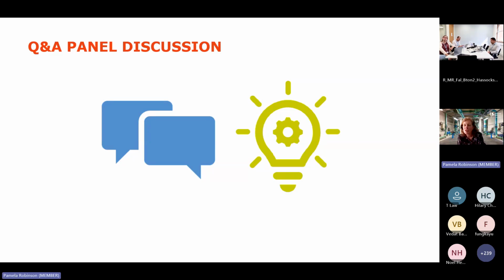Thank you, Chloe. Is there general guidance for head loss values for different types of valves? Look at the manufacturer's guidance. The ones we normally spend most time looking at for head loss, which is important for sizing, are the control and regulator valves, like butterflies and eccentric plugs. In the data sheet you get from the manufacturer, it will give you the K values, which are a measure of flow restriction and head loss across them, and the charts of head loss against percentage opening and flow rate. Different manufacturers will be slightly different just because the shape and dimensions are going to be slightly different. So there are rough guidelines in various literature around, but if you want the truly accurate ones, speak to the manufacturers.